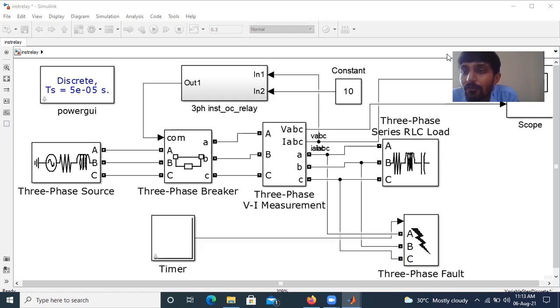It will not wait for any kind of confirmation like a time delay or inverse time. Whether the current gradually rises or decays does not matter, but the relay will open when our current exceeds 15 ampere.